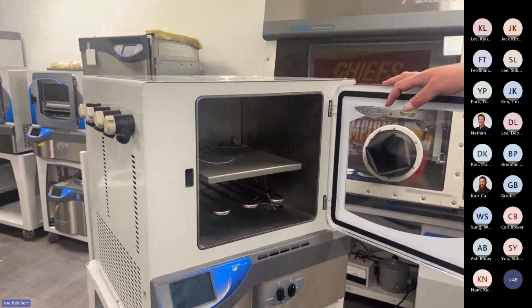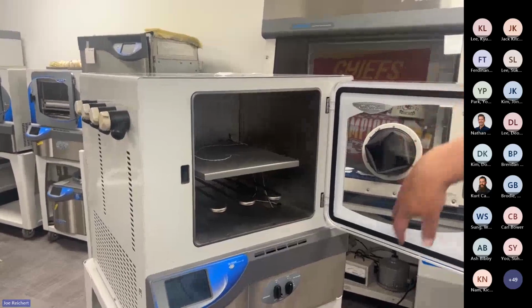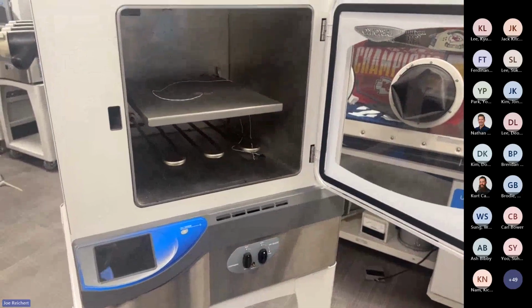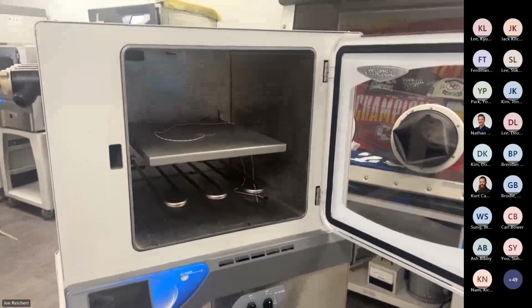So when you have customers that are using max cold to pre-freeze samples and it goes to -75, it removes all the gas from the collector and shoves it into the shelf. So your display reading will have dashes for the collector during max cold mode. And then your shelf is to get to -75.